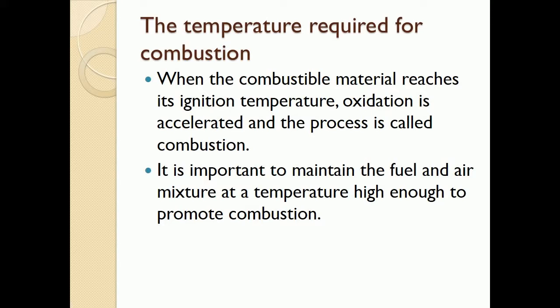Also, if the fuel contains moisture, the moisture must be driven off before a fire can take place. The combustion air temperature in the modern boiler is increased to over 500 degrees by the air heater, which uses the temperature remaining in the flue gas after it leaves the boiler to increase the combustion air temperature.